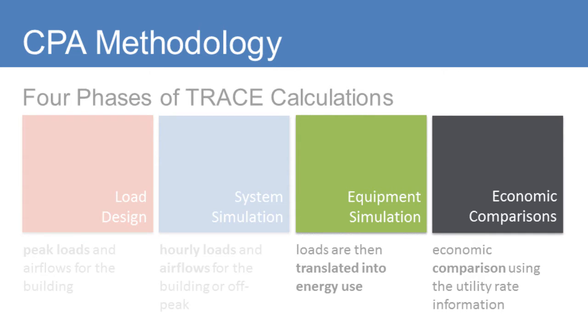During the equipment simulation phase, Chiller Plant Analyzer takes the peak loads of the building, combined with the equipment selected, the part load curves, pump energy, full load equipment energy rates, and so on, and uses this data to calculate the consumption and demand of the chiller plant. You will not enter in each room, wall, window, construction type, etc., which saves about 90% of the time it takes to create and run the file.